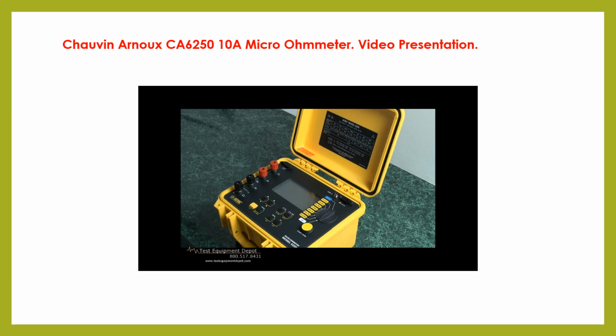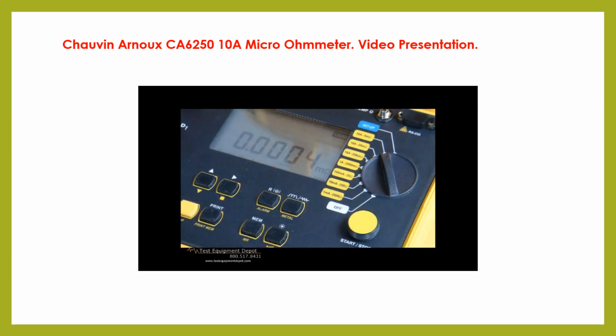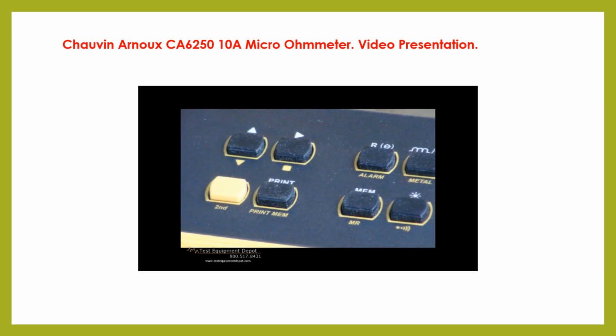It has test current capability because when we're testing a junction or bond, we want to pass current through that bond to stress the connection, if you will. One can walk up to 2 20-gauge wires touching and measure with a classic ohmmeter, and you'll read 0 ohms. That is not a good connection. It will not support any kind of current, and in the case of lightning protection, things like that, you want something with excellent bonding capability, very low resistance to carry away a lot of energy.